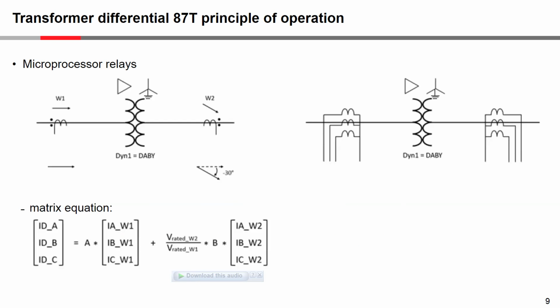So if we go now to microprocessor-based relays, which is where we are today, there you can see we have a matrix equation now that is handling all of this. And so that's the first point. And the second point is that now, because everything is handled in the matrix equation, the CTs on both the delta and the Y side can be directly Y connected to the relay.